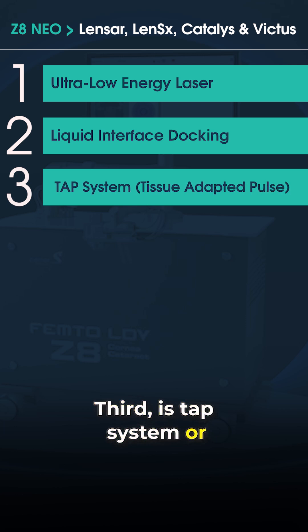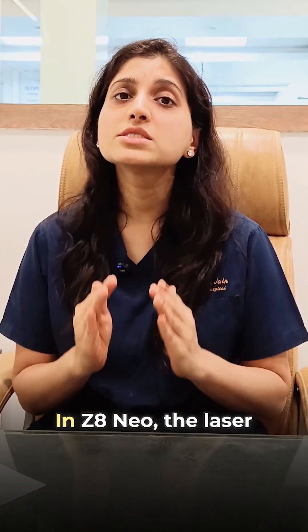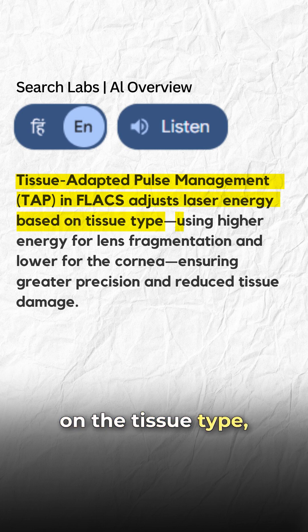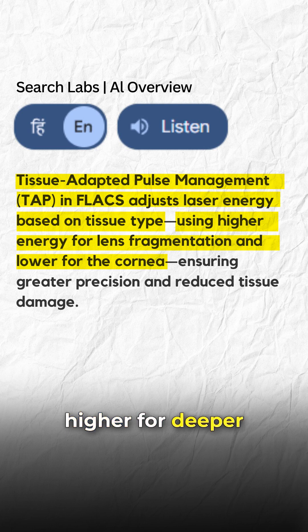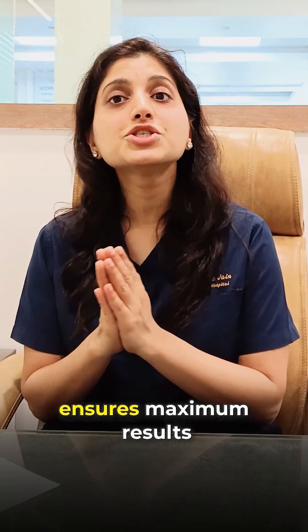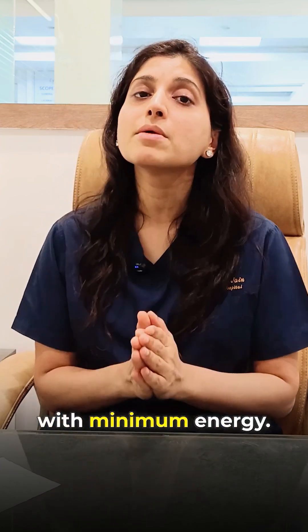Third is the TAP system, or tissue-adapted pulses. In Z8 Neo, the laser energy automatically adjusts based on the tissue type — using low energy for superficial layers and slightly higher energy for deeper tissues. This customized step-by-step energy delivery ensures maximum results with minimum energy.